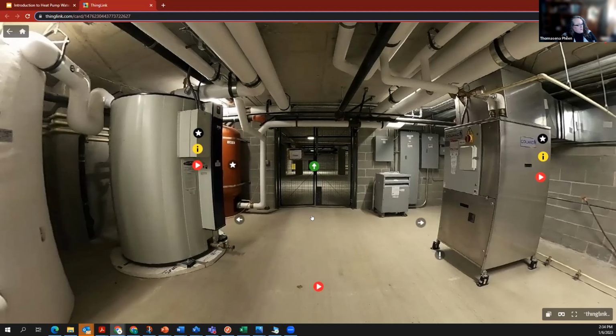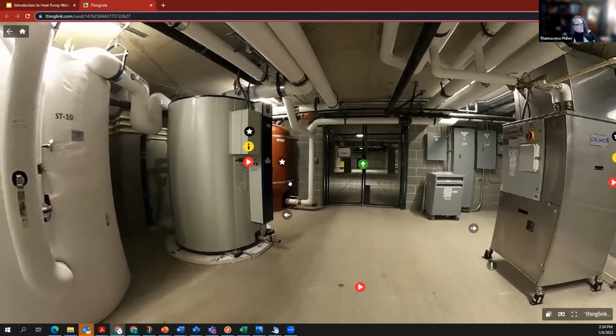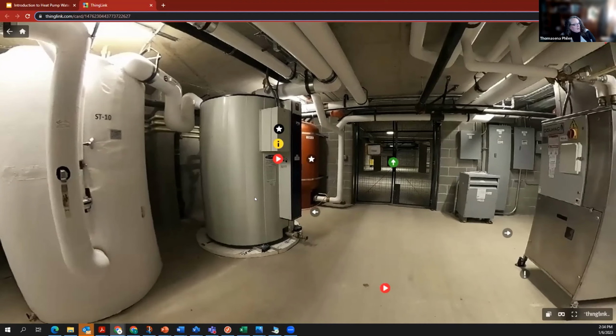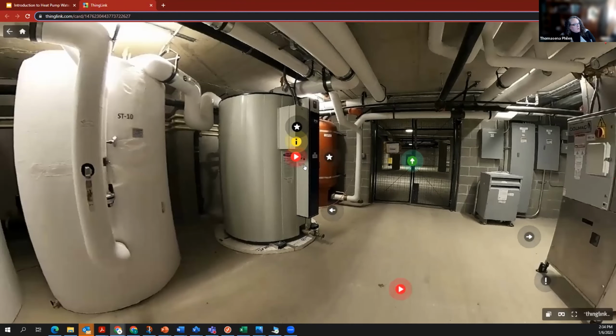This is the heat pump. If we went to the left here, you'll see that there is a temperature maintenance tank. And I'd like to spend a moment or two just to discuss temperature maintenance, because in apartment multifamily systems, multi-floor multifamily systems, they have to have a recirculating pump. So that pump is circulating water throughout the building. Now, once that water goes all the way up to the top and then all the way back down, it could have lost about 20 degrees of heat in that water. So this tank is dedicated to just topping off the temperature of the water that's recirculated in the building.